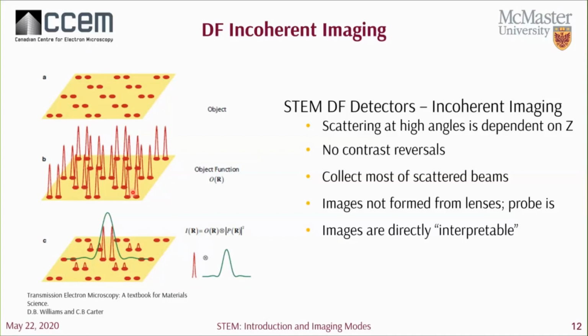But anyway, when a probe comes along, shown here in green, the potential of the scattering is weighted to the probe intensity, and the image can be mathematically described by the cross correlation of the object function and the magnitude or the intensity profile of the probe. So this definition of incoherent imaging tells us that the image that we see is a representation of the scattering cross section and the probe. And since the signal is integrated over the entire detector, any phase information in the object is destroyed.